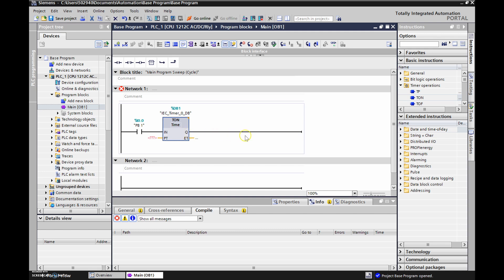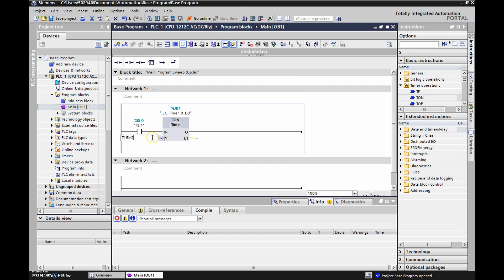The output is Q. Over here we have our preset value. Let's double click on that and open it up — maybe we can put five for five seconds. As soon as I put the five it changed it to five milliseconds, so let's change that to five seconds. The default is in milliseconds and we had to change it to seconds. This accumulated value field we can just leave blank.